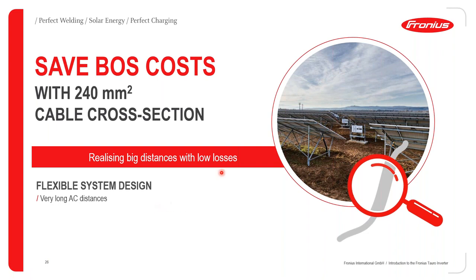to use, because at the end of the day, the total cost of ownership has a relationship to the system losses that you encounter on a daily basis. So if you design a system for 1 megawatt and you have losses of up to nearly 50 kilowatt, something like this, depending on the cables, then your return on investment takes much longer, and that also affects the total cost of ownership and makes the ratio go slightly higher than would be recommended.